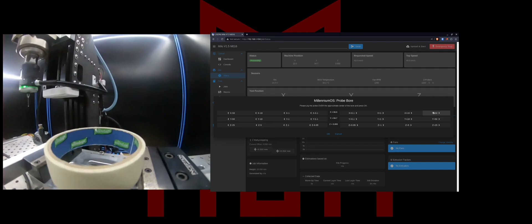I'm going to go down, and if I enter 10 here, that's a positive value meaning how far down we're going to go into the bore. When I hit OK, it explains the probe will move 10 millimeters into the bore and probe outwards towards the edge in 3 directions.